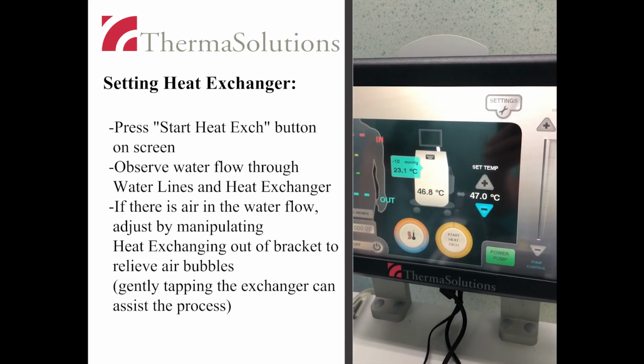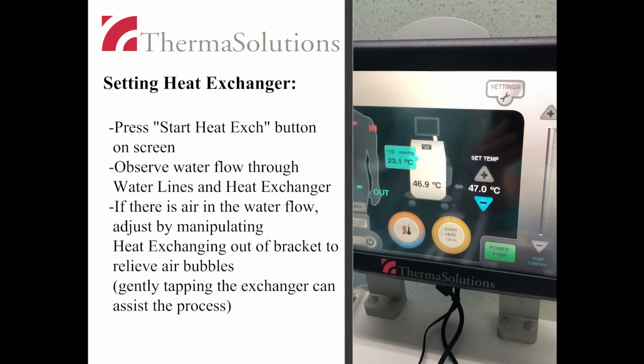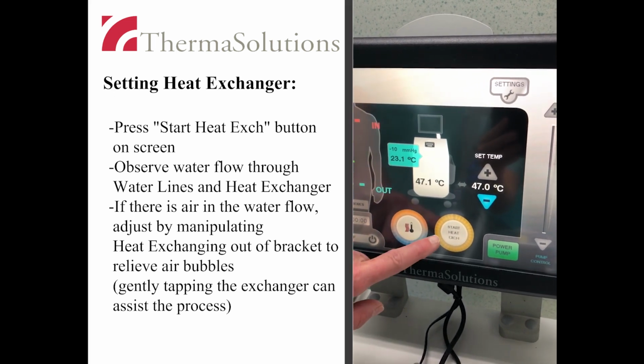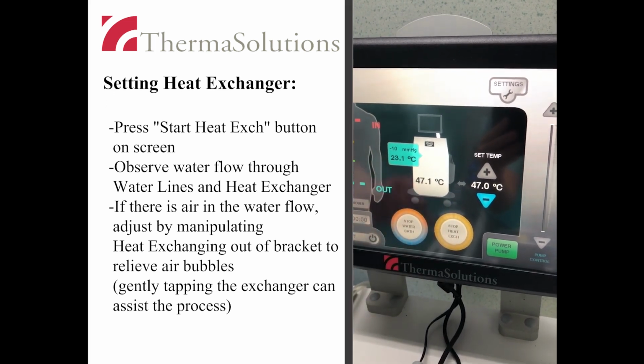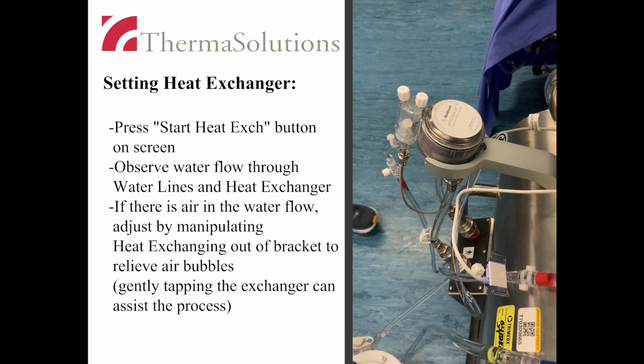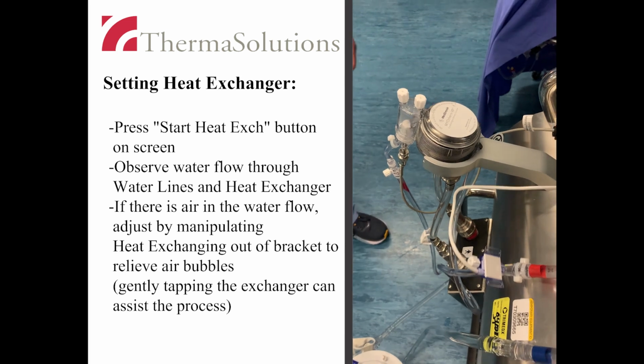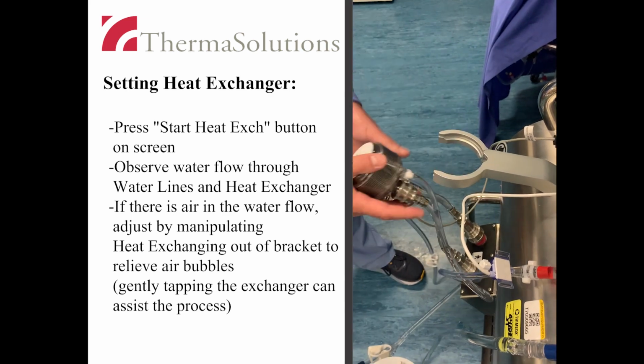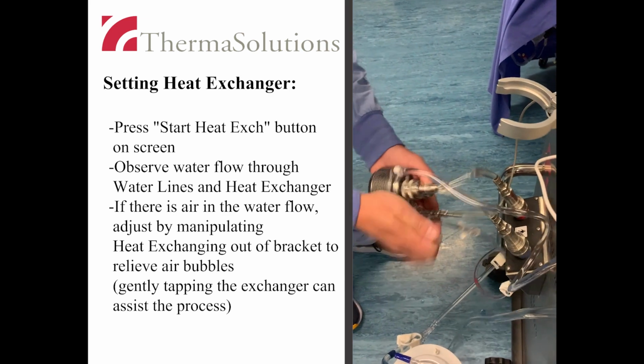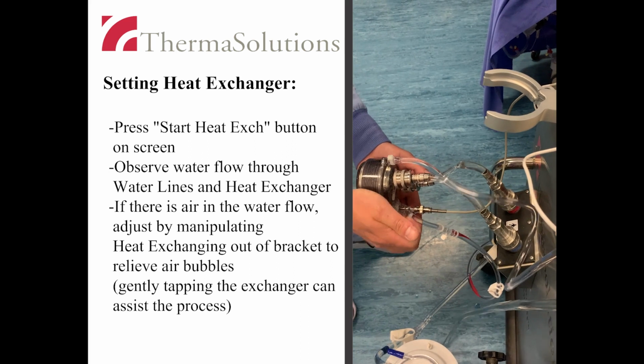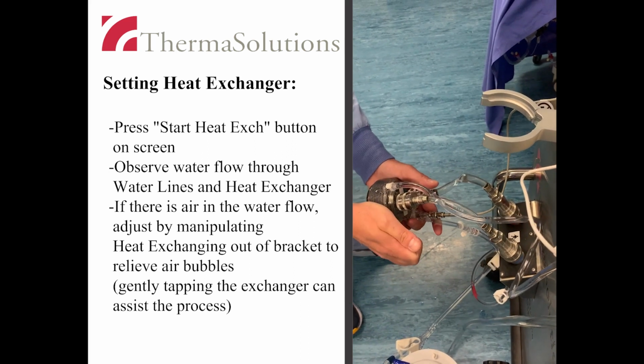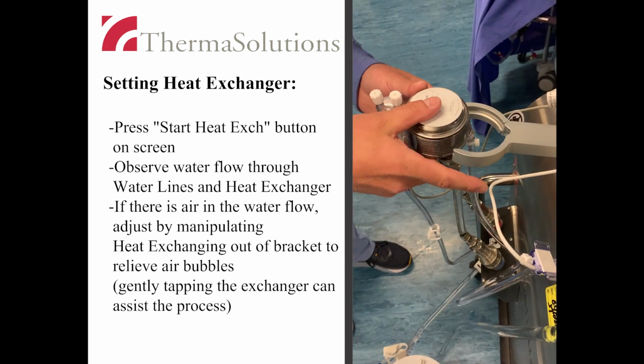Start the pre-warming of fluid through the heat exchanger by touching the Start Heat Exchange icon on the home screen. Observe the water flow through the water lines and heat exchanger. If there is air in the water flow, relieve it by manipulating the heat exchanger out of the bracket to clear any bubbles, and also by gently tapping the exchanger to assist the process.